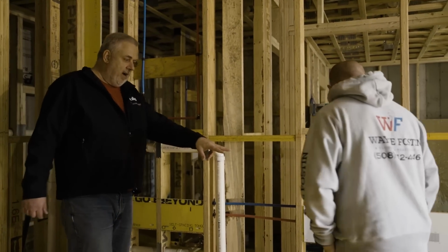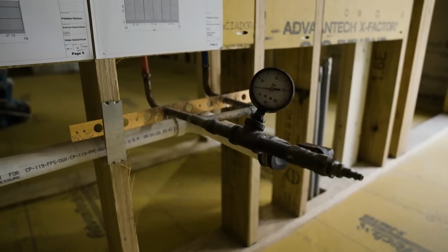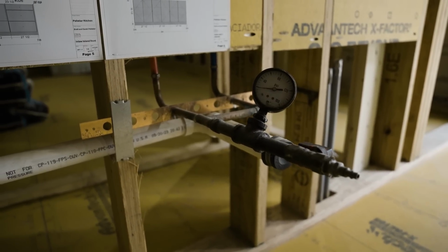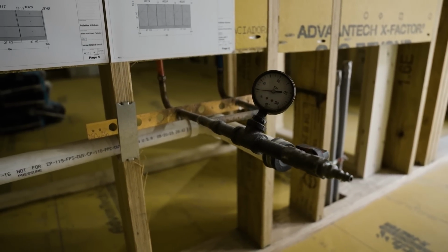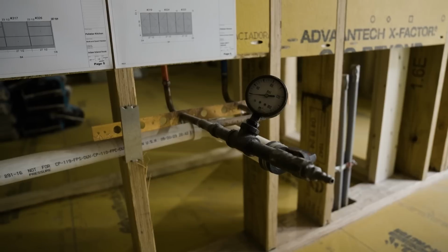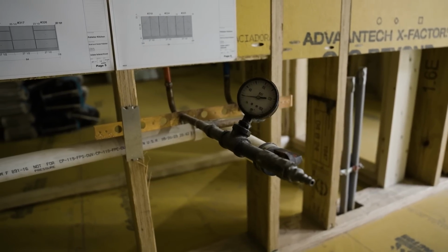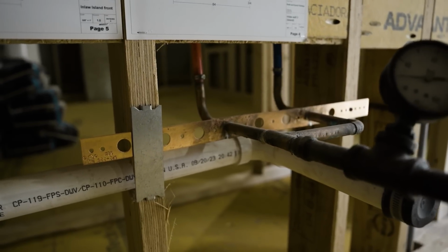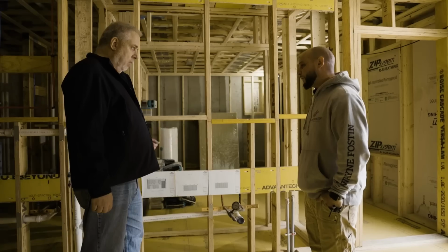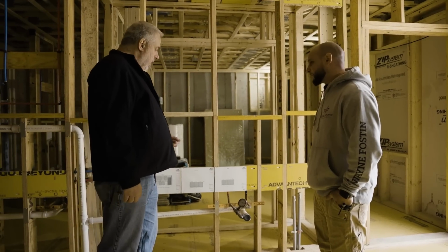Those aren't leaking at all. We put everything on an air test, pumping the house up to 120 PSI, basically double the working pressure. This is a typical setup we put on a rough-in, pumping air in to test all the lines to make sure they're good for the finish. We usually test for a couple hours and then you're all set.